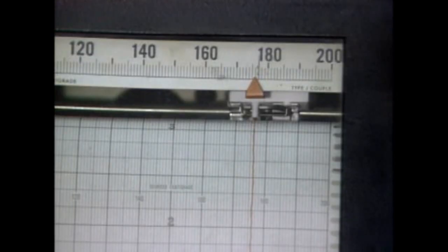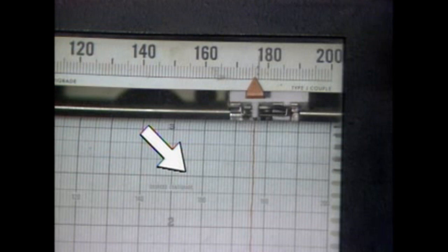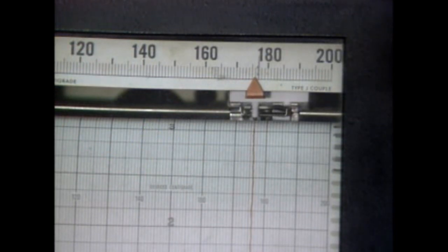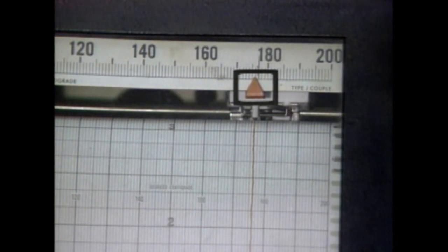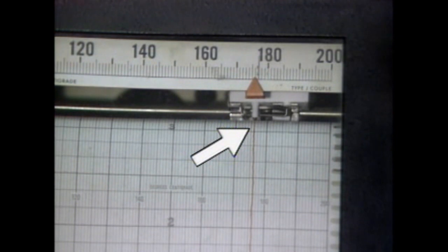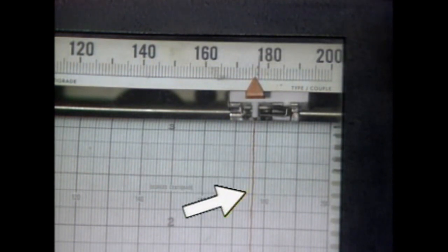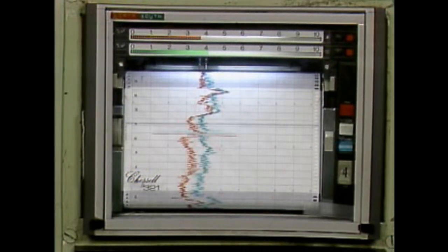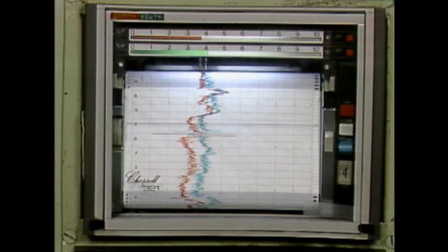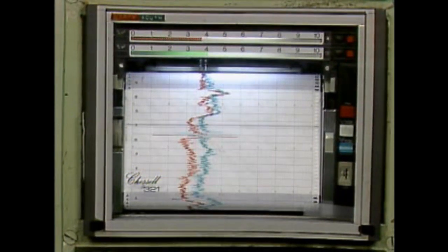This particular instrument is called a strip chart recorder. It has a paper chart that moves slowly through the recorder during operation. A pointer at the top of the recorder indicates the present value of the variable being monitored, while a pen marks on the paper chart, creating a graph that shows the value of the variable over a period of time. Some recorders can record the values of several variables at the same time, or the same variable measured at several locations in the plant.